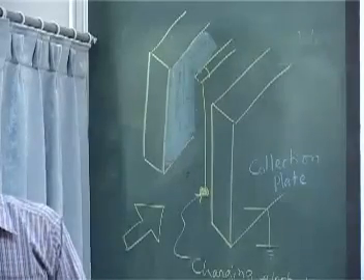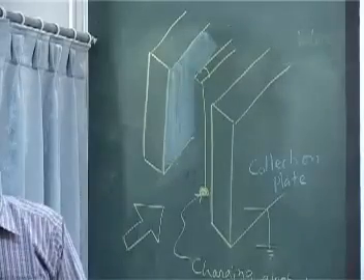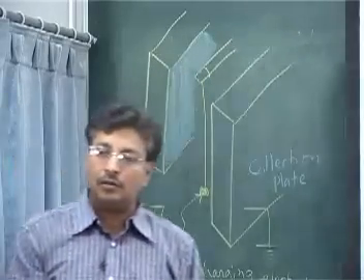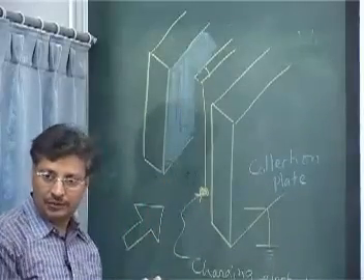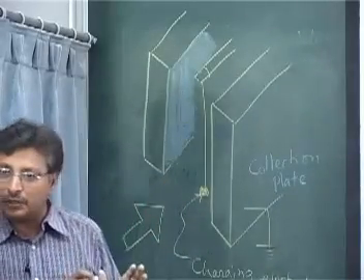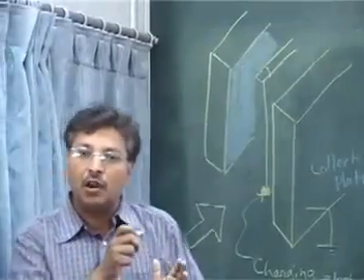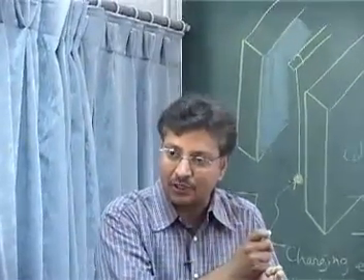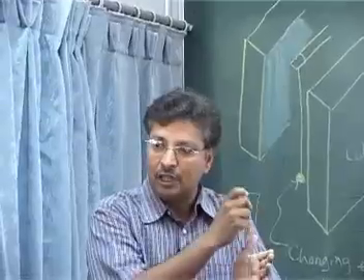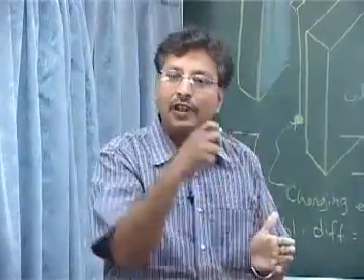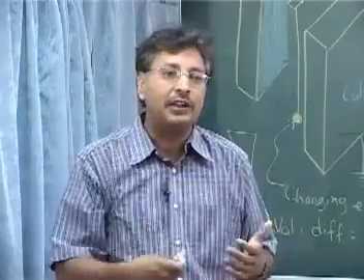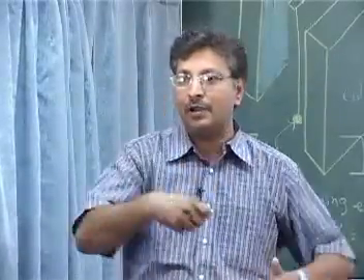What is the mechanism of electrons being attached to the dust? The electrons, as they are moving away from there, have lost more or less their energy. They are traveling slowly, and as they encounter the particles, they stick to them, just physical sticking. They are not necessarily knocking off anything from the particle. They don't have that kind of energy to knock something off the particle and sit there.